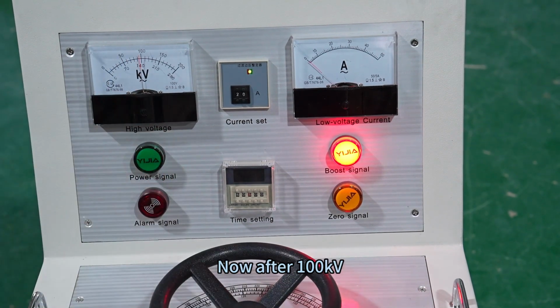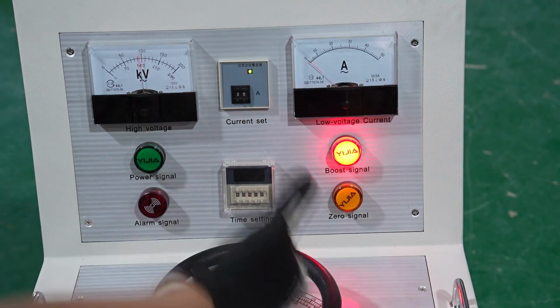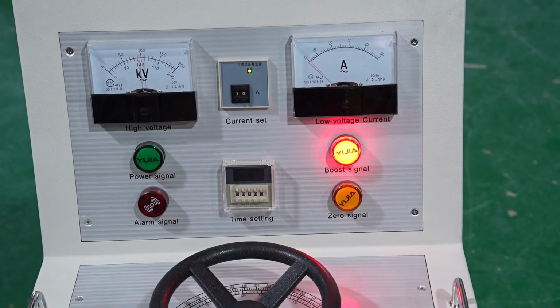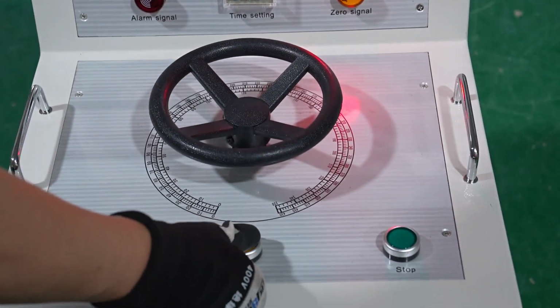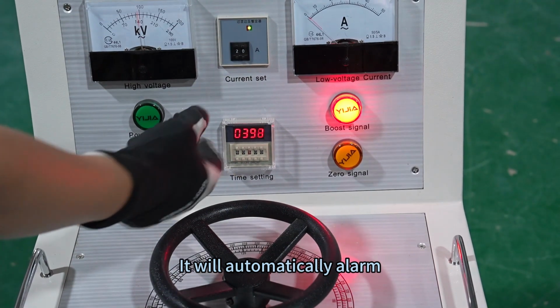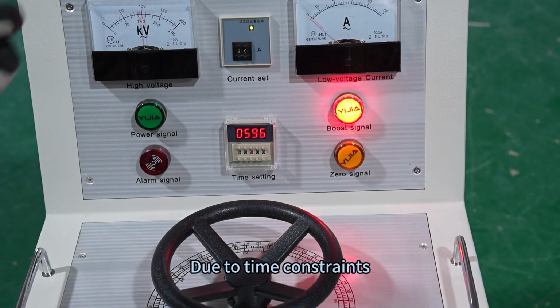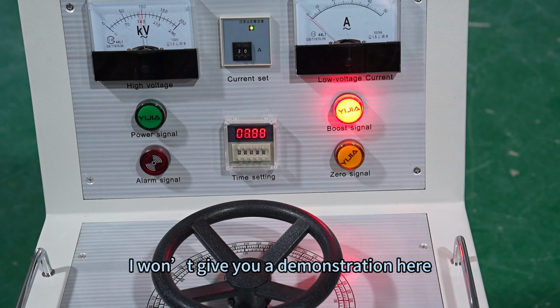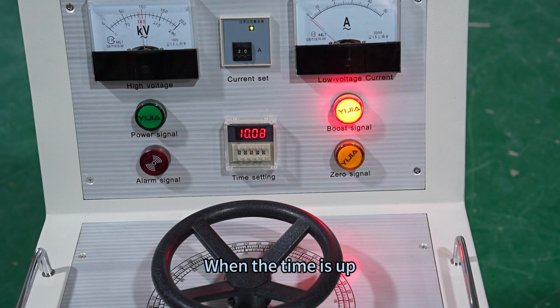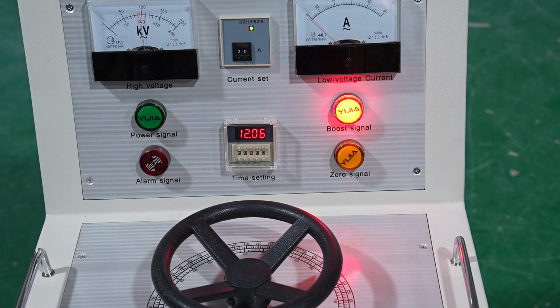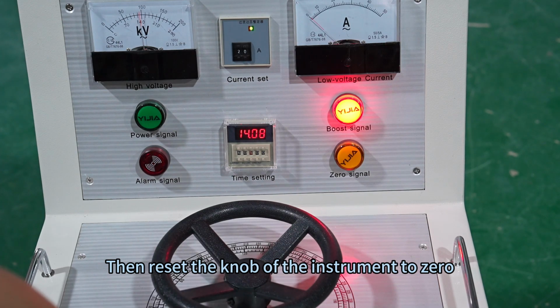Now after 100 kV, we set the timer here. Turn on the timing switch. Start the timer. When the time is up, it will automatically alarm. Due to time constraints, I won't give you a demonstration here. When the time is up, we'll just turn it off. Then reset the knob of the instrument to 0.